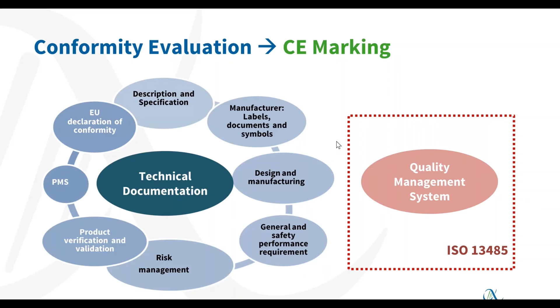In any case, the CE certification requires that both aspects be reviewed, because the ultimate idea is that not only does the device compliance need to be demonstrated, but it needs to be ensured that the quality management system in place is adequate to guarantee that any manufacturing run, so that any subsequent industrial batch, will continue complying with the device specification and will meet everything that is described in the technical documentation. So these are the two main ends of a CE certification procedure.